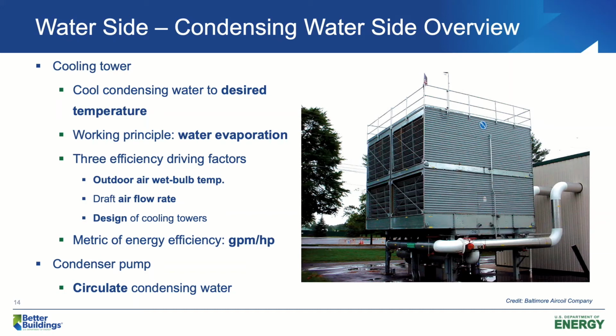Similar to chillers, we also have three driving factors that affect the efficiency of cooling towers: outdoor air wet-bulb temperature, draft air flow rate, and the design of cooling towers. When the outdoor air wet-bulb temperature is low, our cooling tower fans do not need to work as hard to make cool condensing water, so our cooling towers will be more efficient. If we can draw more air flow rate through cooling towers, we can make cooler condensing water. The efficiency of cooling towers also depends on the configuration of cooling towers, either cross flow or counterflow. It also depends on the manufacturers. We typically use GPM per horsepower to measure the energy efficiency of cooling towers.